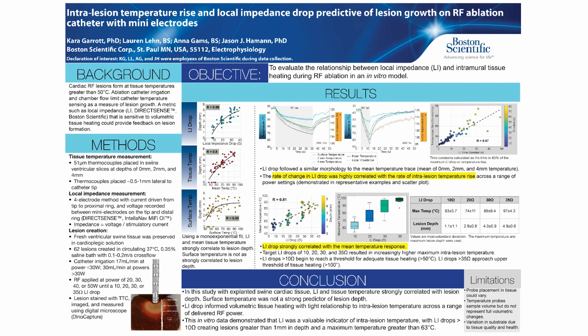We wanted to quantify this rate of change, so we looked at the time it took for both the local impedance drop or the temperature rise to reach 63% of the maximum. And what we see is that overall there's a very strong correlation with the rate of change between local impedance and temperature.